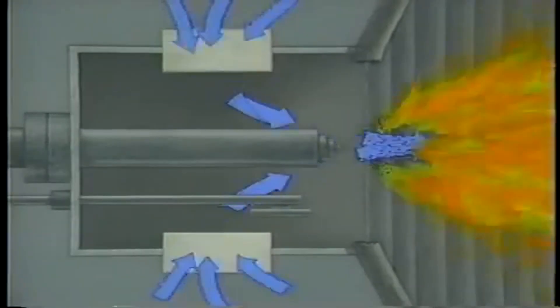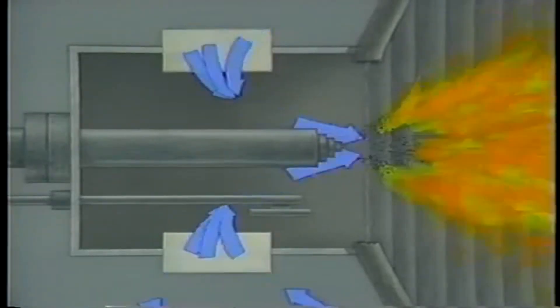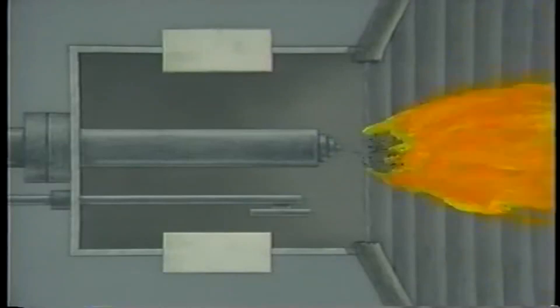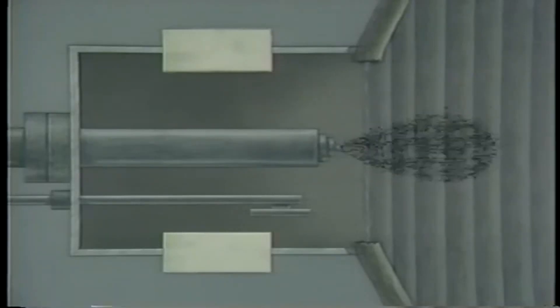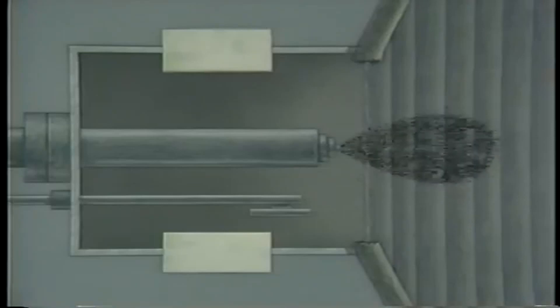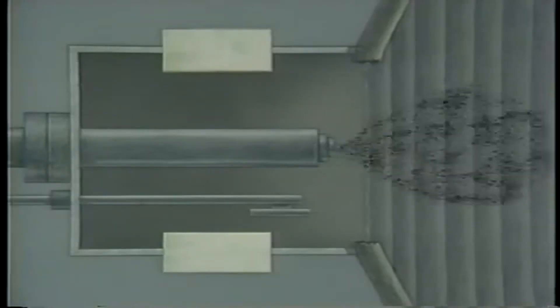If you have established a proper boiler flame and airflow and fuel flow are properly matched, your burners will operate the way they're supposed to. However, if airflow is interrupted, one of the basic requirements for combustion is eliminated. This will cause the boiler flame to go out. Unless the fuel flow is immediately stopped and the boiler is purged, an abnormally high concentration of fuel may accumulate near the burner port. If airflow is subsequently reestablished, this large concentration of fuel can ignite suddenly and cause an explosion. Interrupting fuel flow will also extinguish the boiler flame, and unless steps are taken to correct the problem according to procedures, an explosion may result when fuel flow is restored.